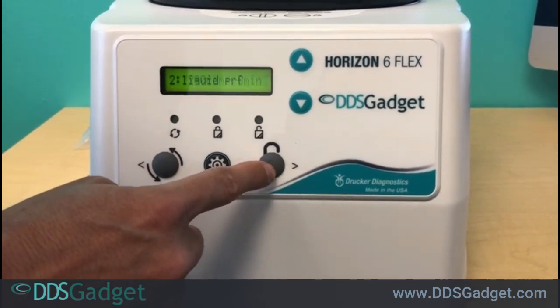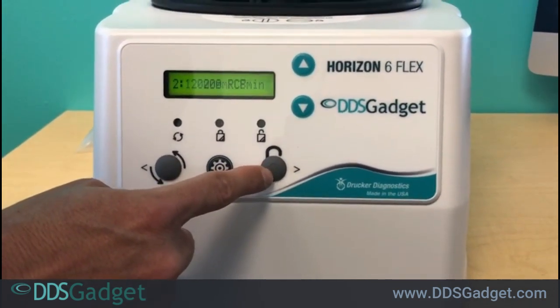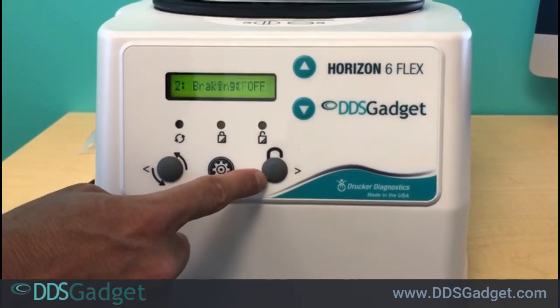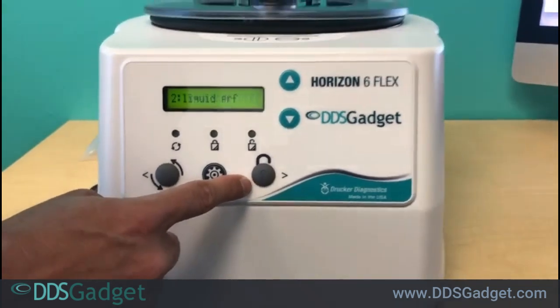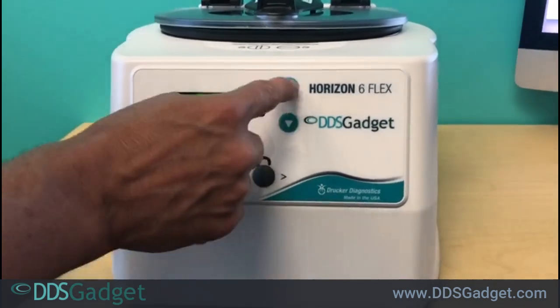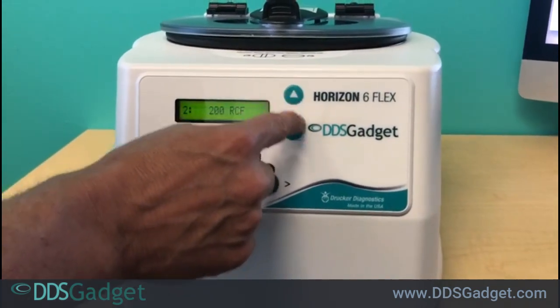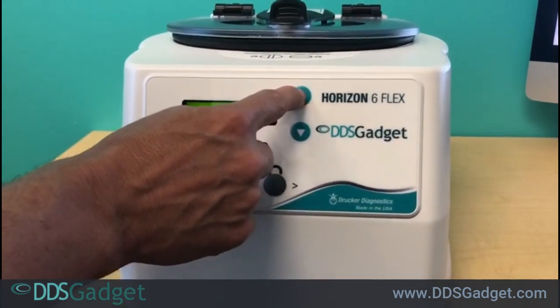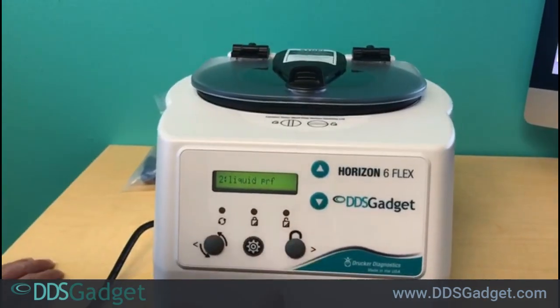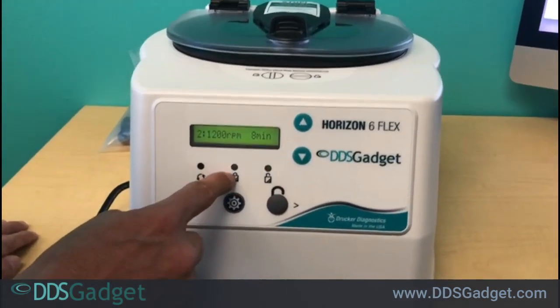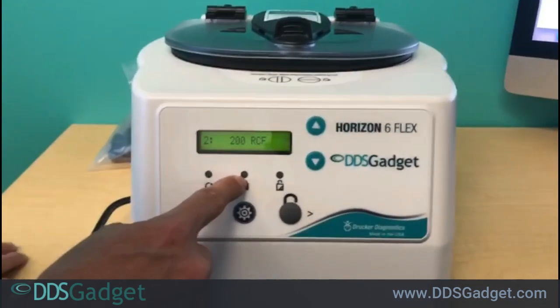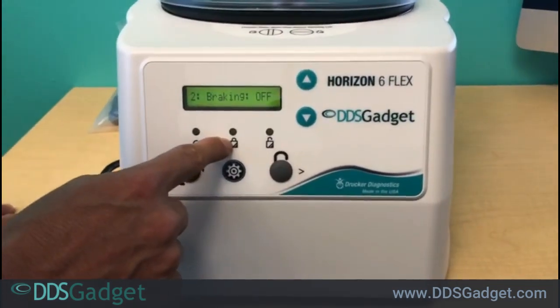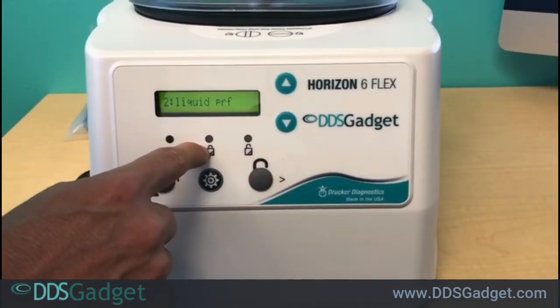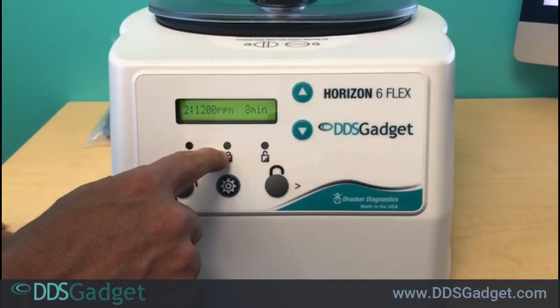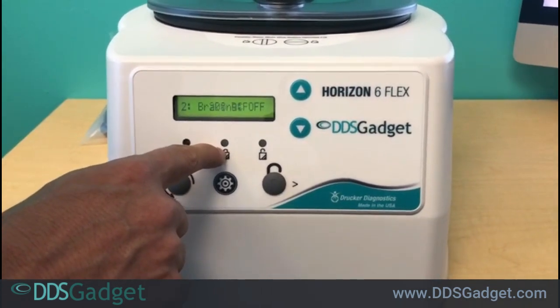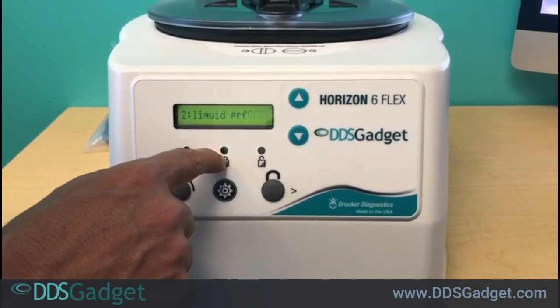This, per the prior video, is the unlock button, which you'll use to unlock the centrifuge after the cycle is done, or if it's your first time turning on the machine, you'll have to use the unlock button. Again, these arrows over here are just to change between the different settings, and you could just choose it like that. The final thing is the lock button. When the centrifuge starts, this lock button will go on, and obviously do not open the centrifuge while it's running. Just wait till it stops, and we'll go over that again in a future video.